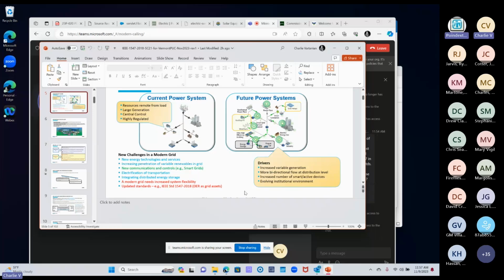direct transfer trip in all cases to assure anti-islanding. So in the near term, traditional protection approaches and schemes - although the engineering required to maintain that coordination is going to get tougher, and it may require going to some electronics versus, for example, fusing relays and breakers. Not solid state breakers, you can stick with conventional, but some smart relays. There will come a time where traditional protection approaches will have to be revamped.